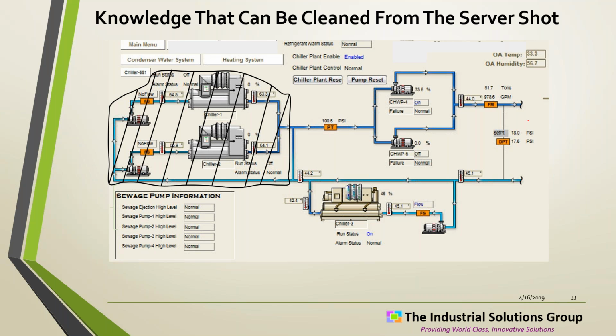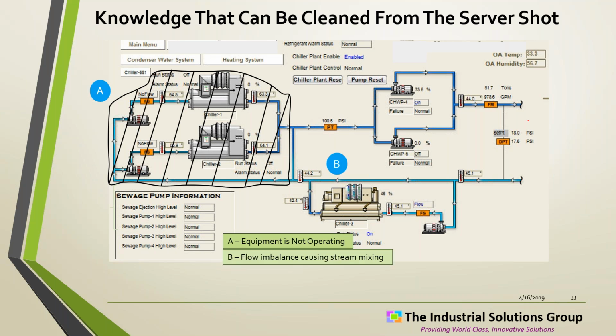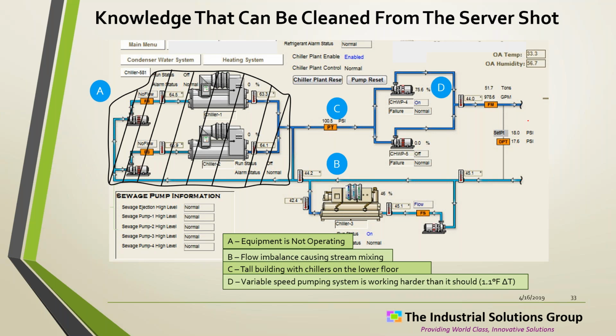And so, those two chillers aren't even running on this day. So equipment A is not operating. They've got a balancing problem going on here. They shouldn't be mixing warm water and cold water with this remaining chiller that's running. So that's a problem that's going to cost them energy. I was just noting that obviously this is a tall building, and this is a basement floor type of installation. I picked that up from the pressures.